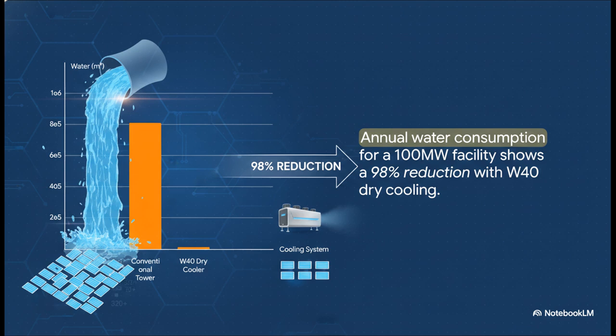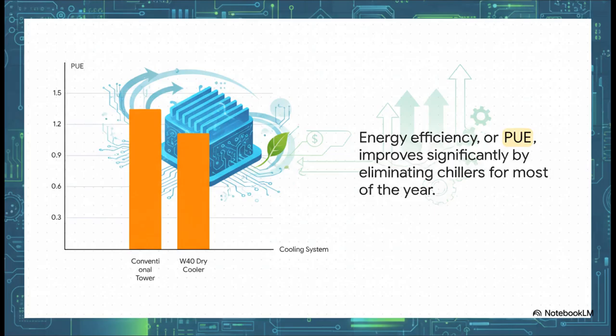The difference is incredible, and on top of that, the system is way more energy efficient. We measure this with PUE, or Power Usage Effectiveness. A perfect score is 1.0, meaning 100% of the power goes to the computers; anything above that is basically wasted on things like cooling. By getting rid of those power-hungry chillers, the PUE drops from a pretty inefficient 1.35 all the way down to a very sleek 1.12. That's a huge cut in wasted electricity.